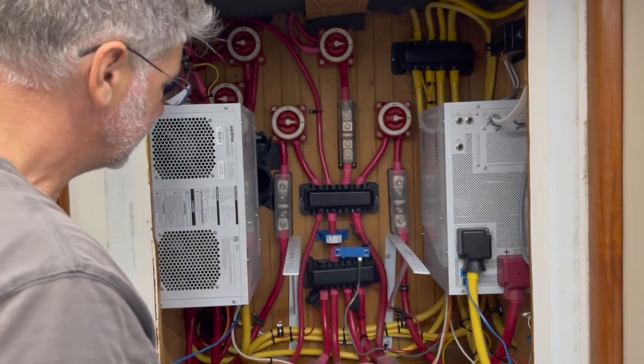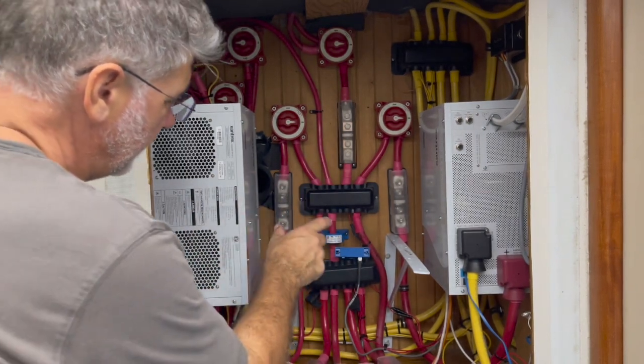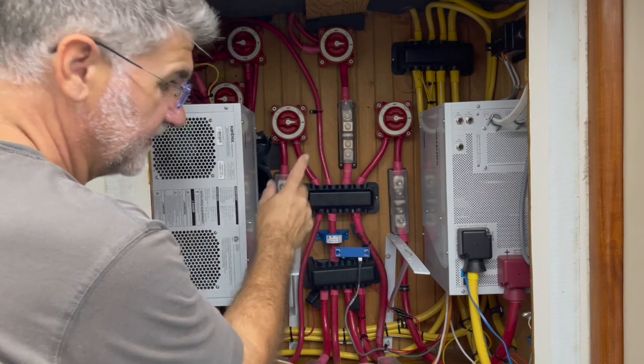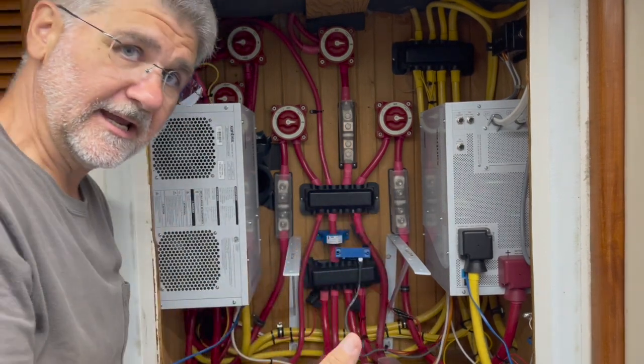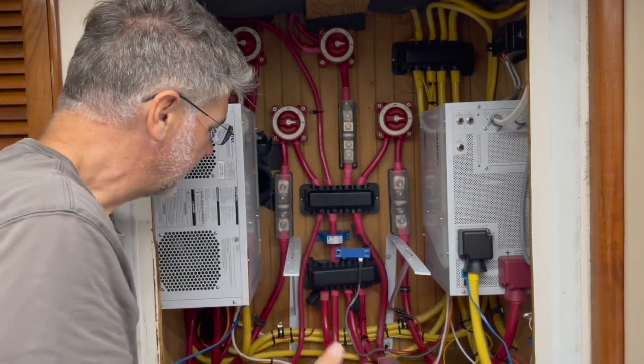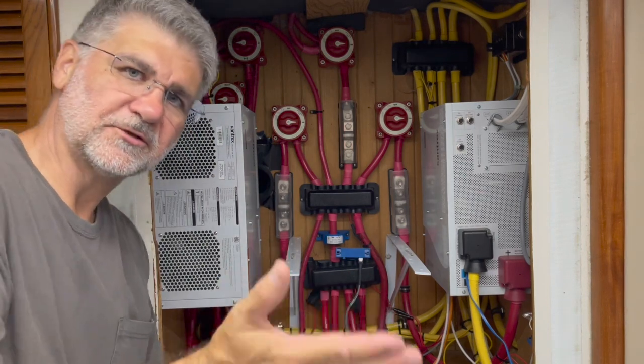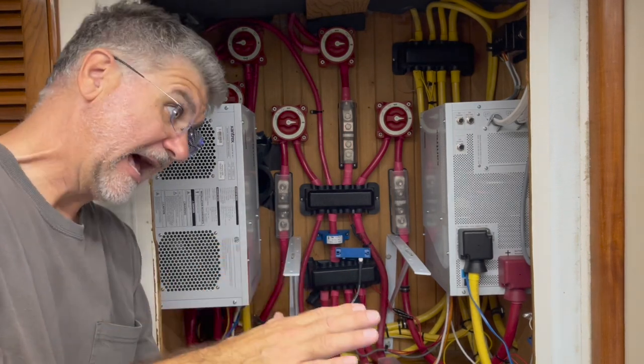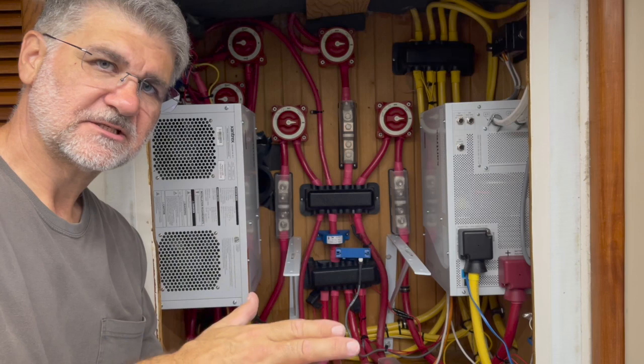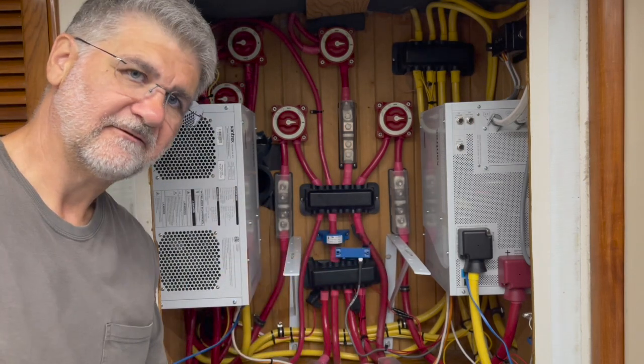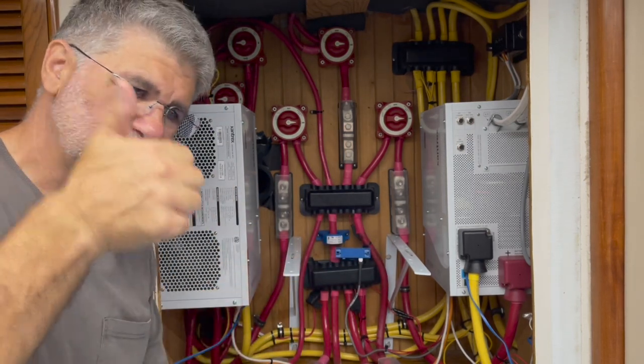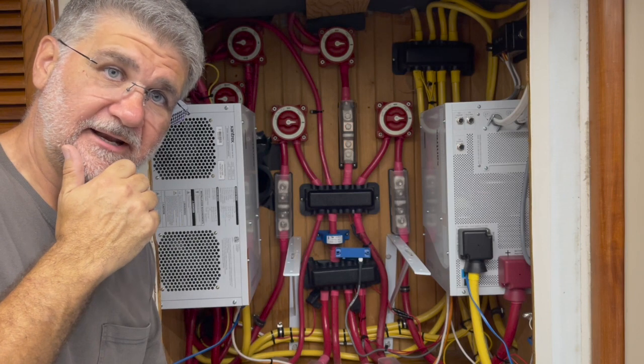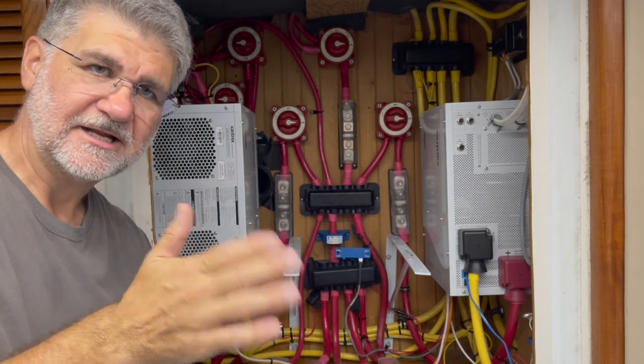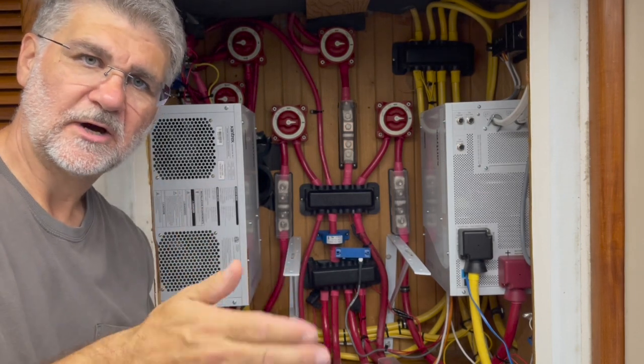I've done everything I need to do with the calibration. After I turn the N2K network off and zero it, I'm going to move it away from a magnetic source and make sure the voltage doesn't change. It shouldn't affect it at all, but before going through the process of including everything, I want to test this. So we're going to go up to the pilot house now and look at the Maretron N2K analyzer, and I'll show you how all this works.